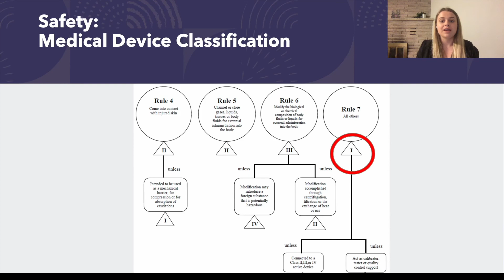In Canada, in order to obtain a medical device license, the device must be classified based on its risk with a class. Class 1 being lowest risk and Class 4 being highest risk. This medication administration device will be Class 1, and this was based on the flowchart pictured on the screen for non-invasive medical devices. As you can see, this device falls under Rule 7, all others, and Class 1 is circled in red.